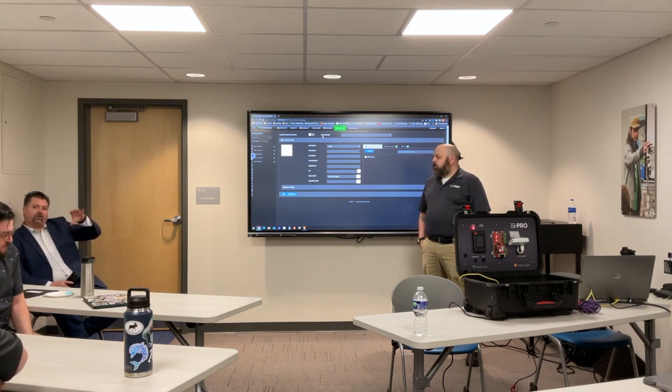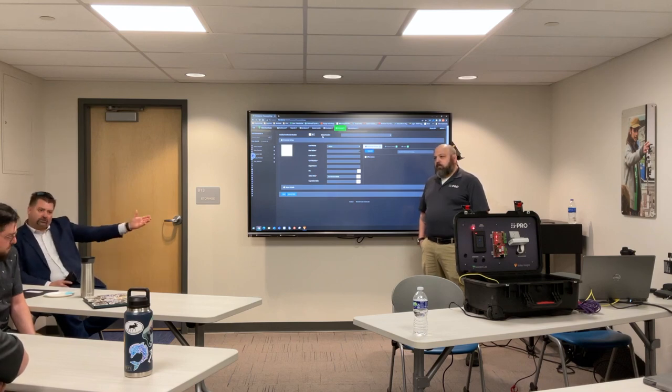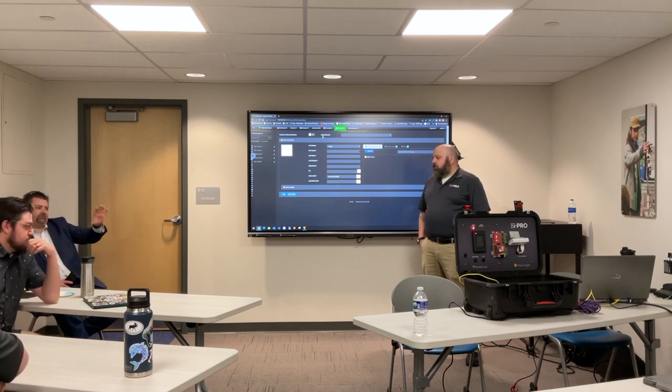Okay. So that puts more work on the controller part of it. The way we proposed it is you got the LP1501 with a life safety power supply, and that has all the relays and does it. So the controller tells the life safety power supply to then do that, and that's a lifetime warranty. If that goes down, you contact life safety, they replace it. So it doesn't put a lot of work on the LP1501, the controller board, because those relays can only handle so much.